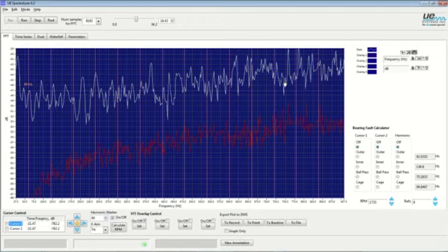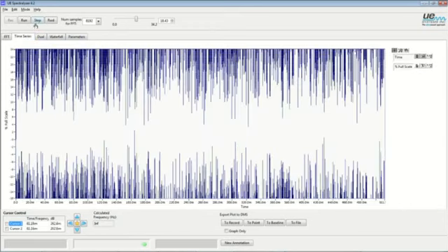That impacts the timing, and it changes the frequency spectrum in the form of masking the outer 60 Hz harmonic peaks. But in this case, I don't see enough 60 Hz peaks to even say there's corona present. But I do suspect that there's going to be an arcing and/or tracking event. To determine that, I need to switch to the time series analyzer here.